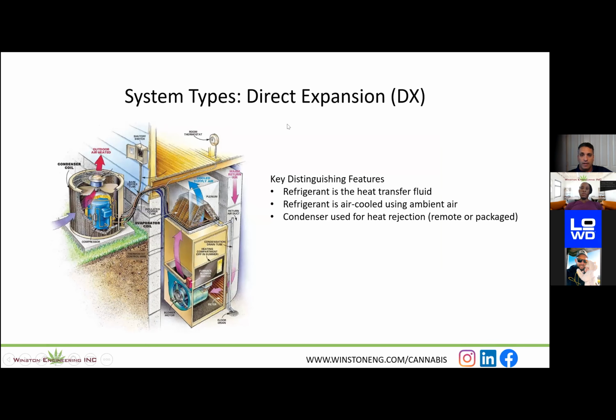And then the third system we're looking at is direct expansion, or DX. So think about your house. I mean, that's a DX system. You have a condenser outside, you have your air handler inside, right? You have a coil inside, that's your evaporator coil, and then you have your condensing coil outside. So your compressors here will pump the refrigerant into the air handler. That refrigerant is going to be really cold. It's going to absorb the heat out of the air from the space and then pump that refrigerant back out to the condenser so that it can again be air cooled by the ambient air, right? So in this case, the refrigerant is the heat transfer fluid, the process fluid, as opposed to chill water.